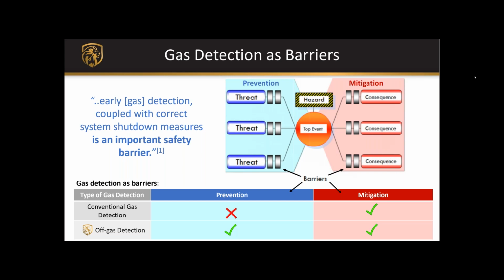There was a 2-year study that DNVGL conducted on marine battery safety, and one of the key findings with respect to gas detection was that early gas detection with the Li-ion Tamer system, coupled with correct shutdown measures, is an important safety barrier for an energy storage system. So we're looking at the preventative side and how off-gas detection systems can act as a barrier to the threats that lead to top-level events.